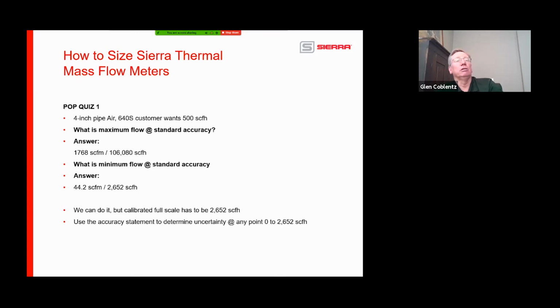Customer may be okay with that. And he says, that's great, I'll go with it. Customer might say, no, I can't live with that. I need to be able to measure to 400, 200, 100. So what would you do in this type of situation? You would sell him a 640i with the ULF calibration. So that way you could actually calculate what the standard feet per minute here is. It's probably like 200 standard feet per minute, because if this is 500, well, it might be a lot less than that. It might be 100 or 120 or something like that.